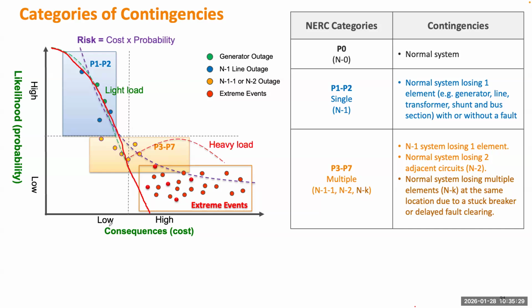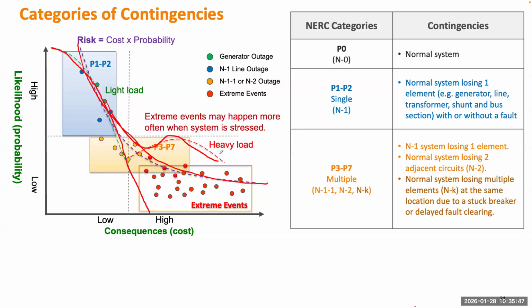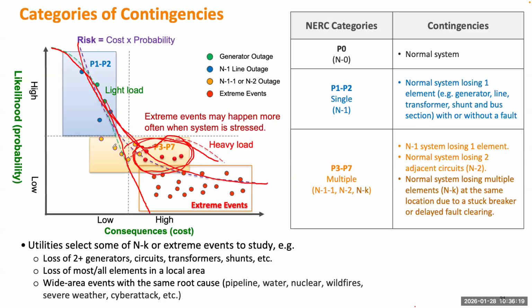But when the system load is high, the risk curve will have a heavy tail, which means it will not be a purely ideal hyperbolic. So maybe at the end, it will just suddenly go up, which means the extreme events may increase their probability. And they will focus on which extreme events can suddenly increase the probability. For example, if the load increases in one area, all the lines sending power to this area will have more probability of being congested. So if you add contingency on those lines, that can trigger more contingencies. So they can focus on some of the N-k scenarios, and then they just ignore the others. Okay, so that's the basic idea of how to select a contingency to study and also cover some of the N-k scenarios. Any question?